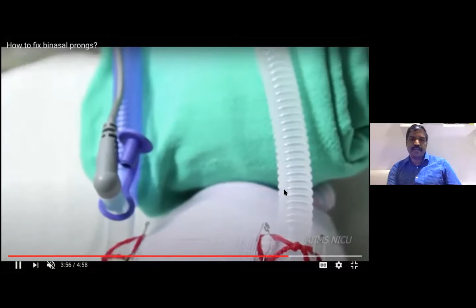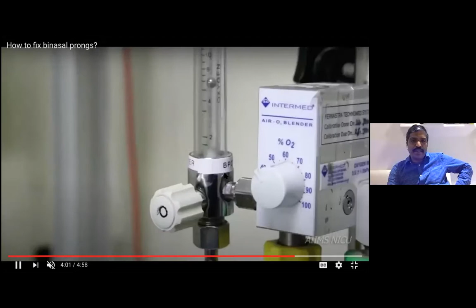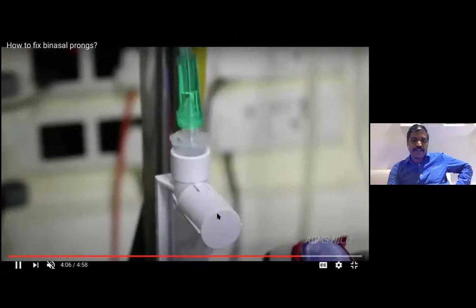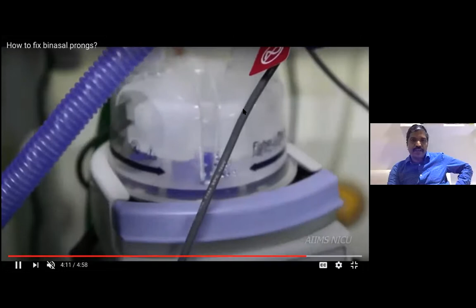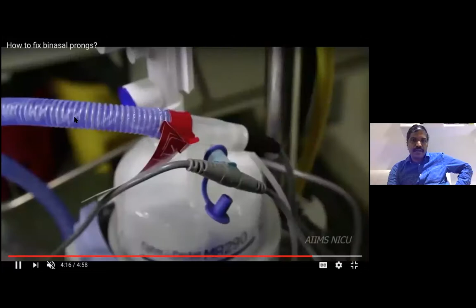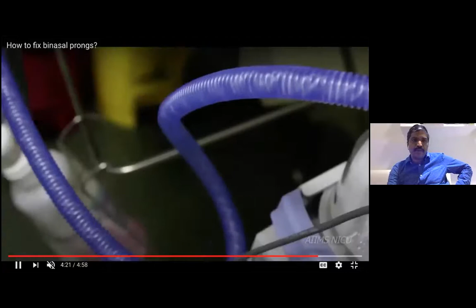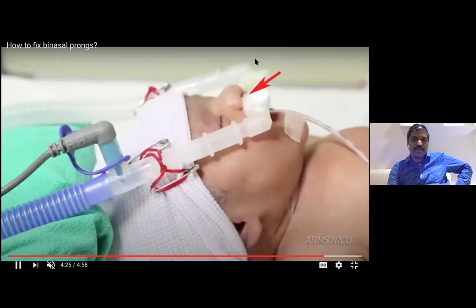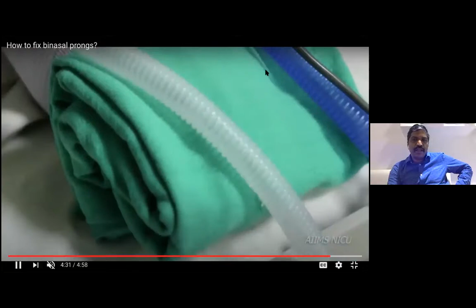Now you can see the complete circuit, inspiratory limb, expiratory limb. Now I am showing again the complete circuit: air, oxygen, blender, flow meter, gas is flowing to the humidifier, the pressure release valve, flow FiO2 monitoring, humidification. Gas is getting heated in the inspiratory limb, and then this gas goes to the patient, and from the patient the gas goes through the expiratory limb to the bubble chamber.